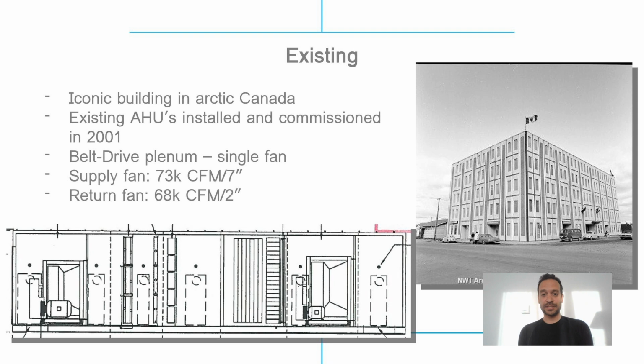Let's go through the existing fans that they had. So they didn't have any redundancy. They had one fan for supply and one fan for return. And as you see, it was delivering air to the whole building. It was a 73,000 CFM on the supply side and around 70,000 CFM on the return side. So they were relying on one fan for all of their cooling and heating of that building.